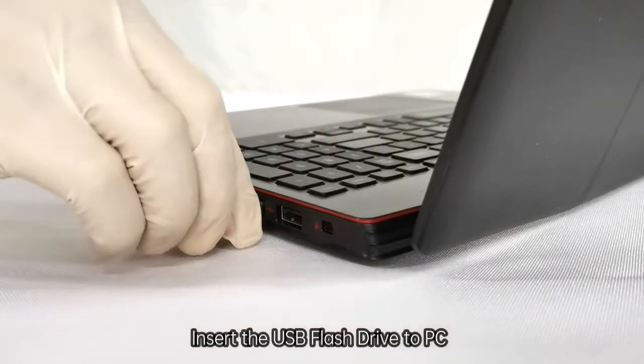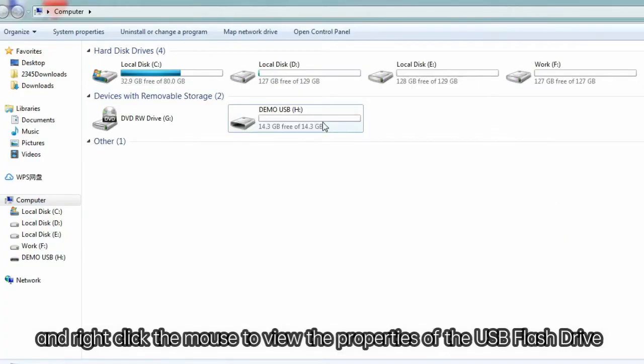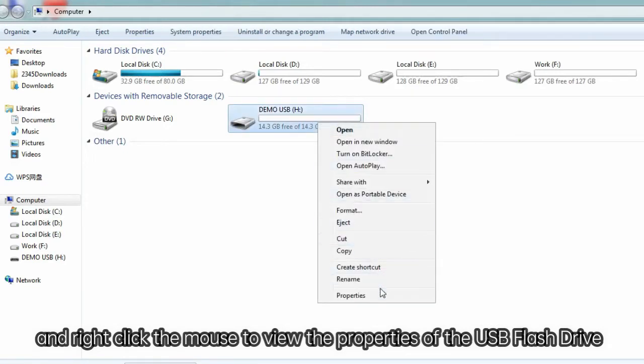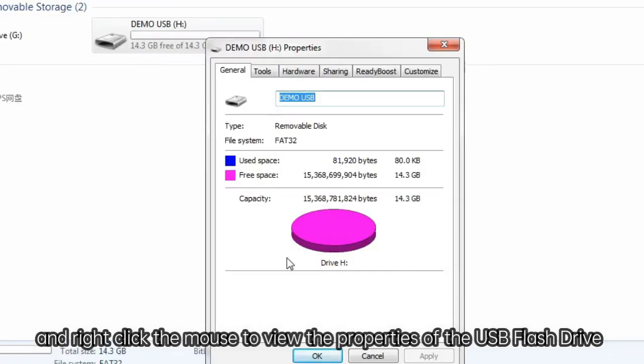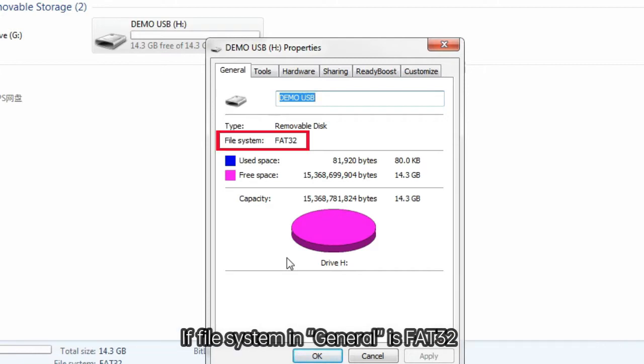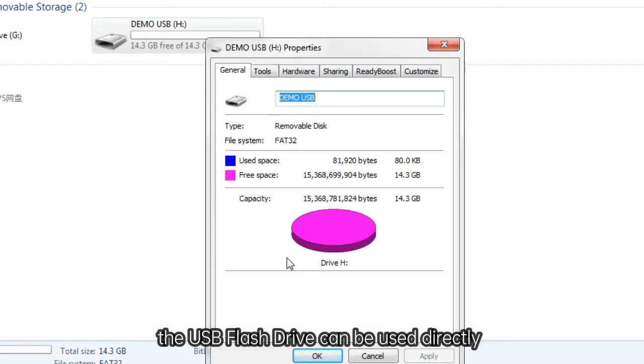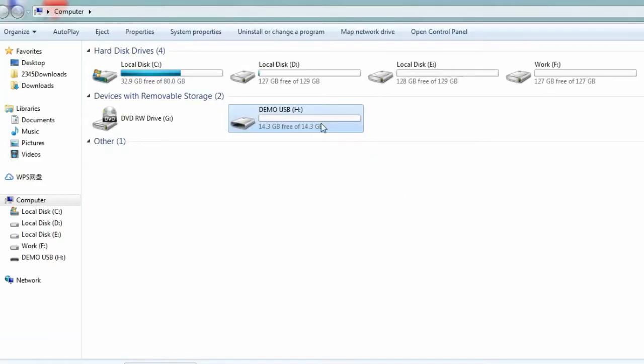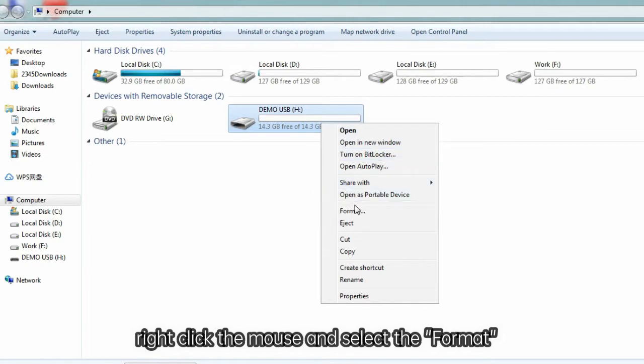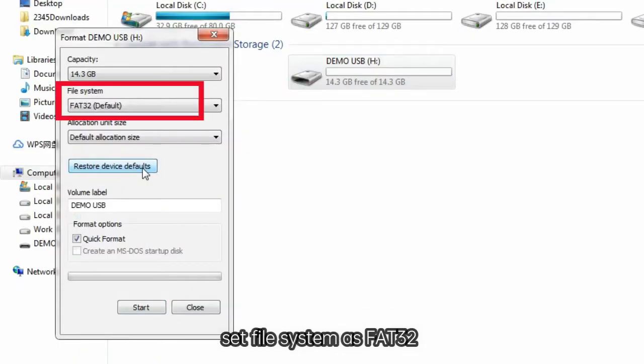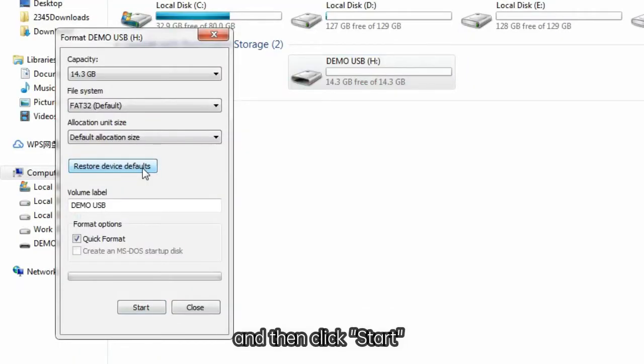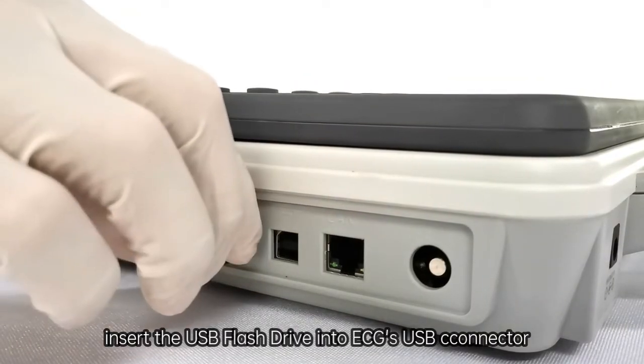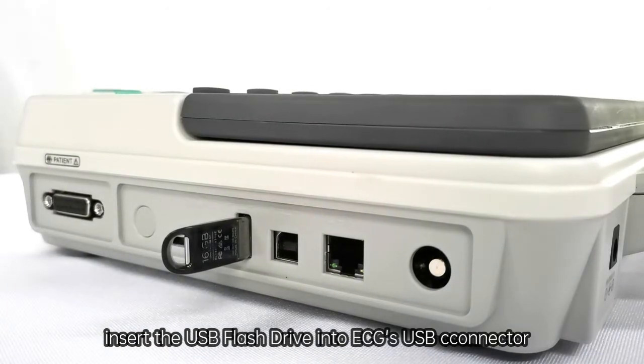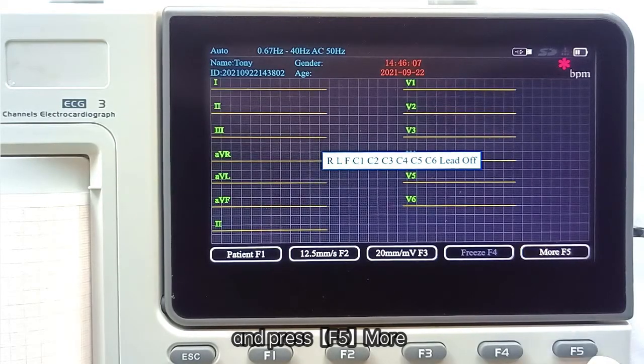Insert the USB flash drive into the PC and right-click the mouse to view the properties of the USB flash drive. If the file system in General is FAT32, the USB flash drive can be used directly. If not, right-click the mouse and select Format. Set the file system as FAT32 and then click Start. After reformatting, insert the USB flash drive into the ECG's USB connector and press F5 More.